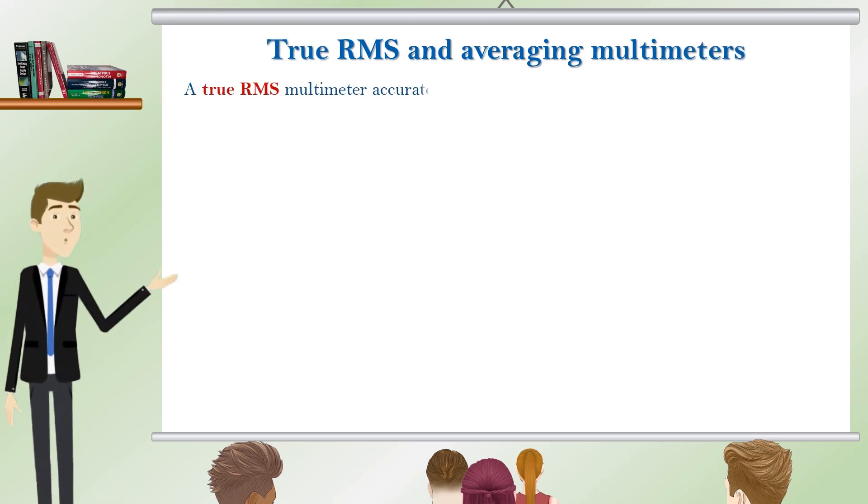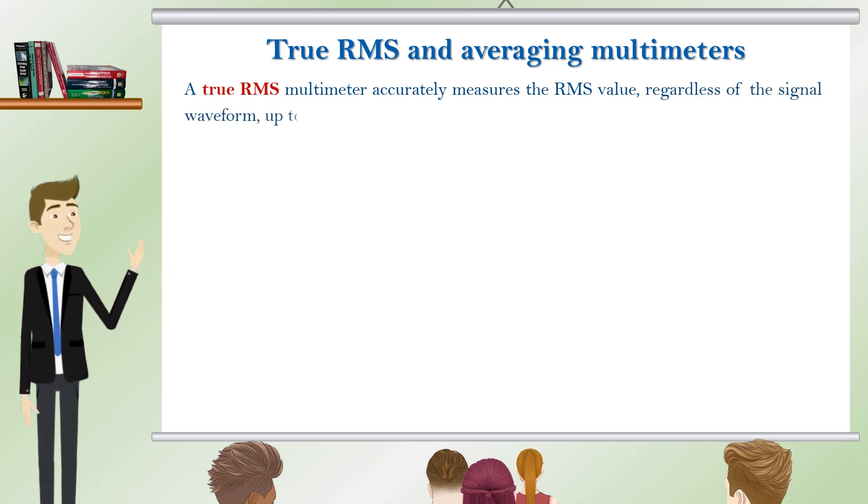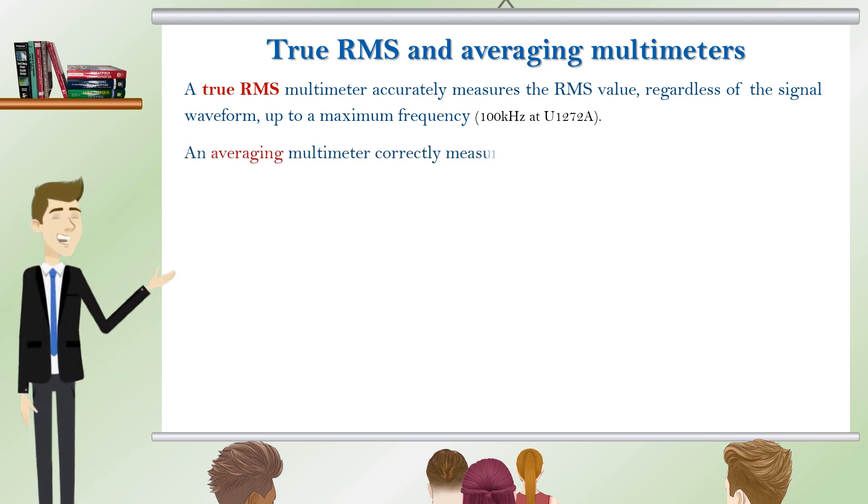A true RMS multimeter accurately measures the RMS value regardless of the signal waveform up to a maximum frequency. An averaging multimeter correctly measures the RMS value only on sine waves.